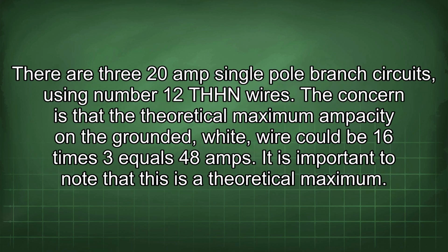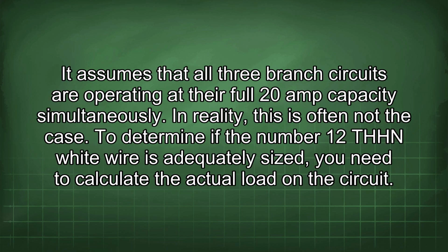There are 3 20-amp single-pole branch circuits, using number 12 THHN wires. The concern is that the theoretical maximum ampacity in the grounded, white, wire could be 16 times 3 equals 48 amps. It is important to note that this is a theoretical maximum. It assumes that all three branch circuits are operating at their full 20 amp capacity simultaneously. In reality, this is often not the case.